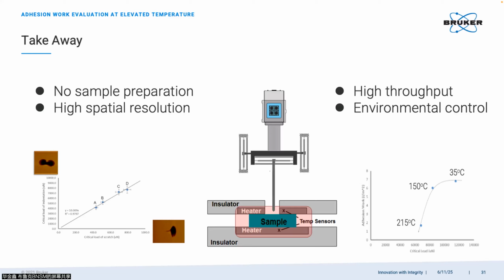But one very critical drawback of AFM for force measurement is that AFM uses a cantilever with an optical lever. They are actually measuring the bending angle of the AFM cantilever. It's not a direct force measurement like a force sensor, so theoretically and practically, it's not the same. With nanoindentation, you can always get more accurate, more repeatable force data when the force is in the range. So these are two technologies, not competitive, but complementary. So you need to buy both. It's different.